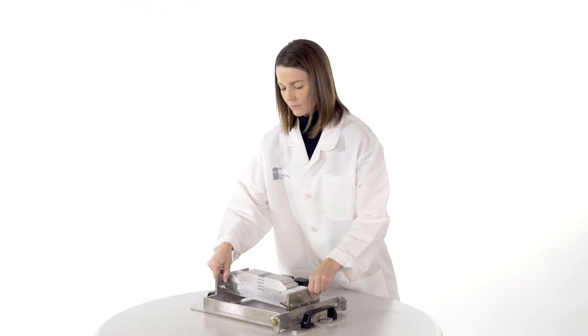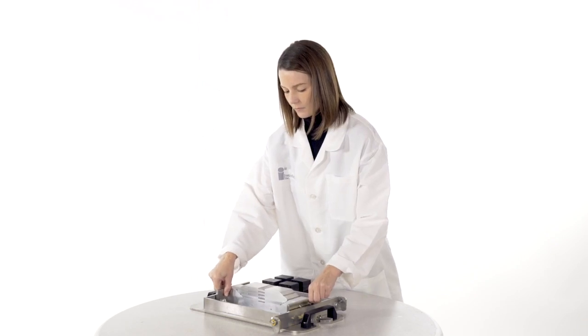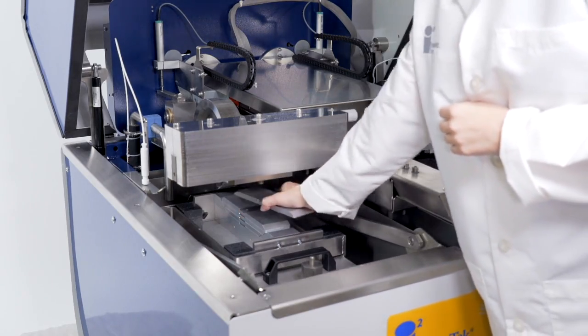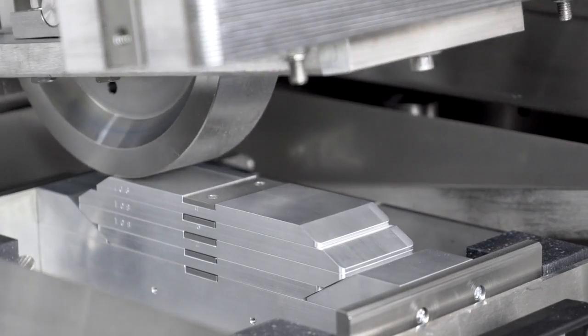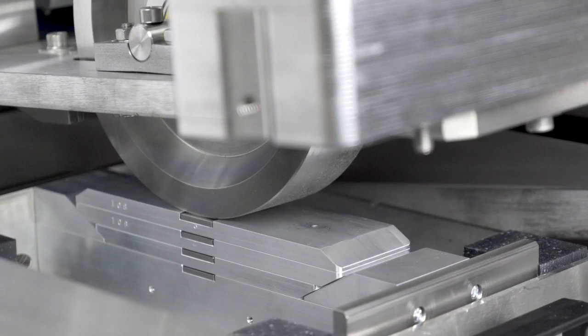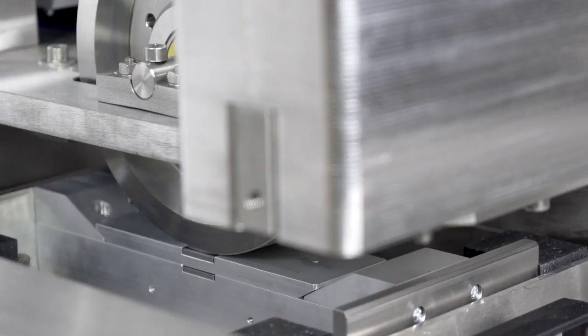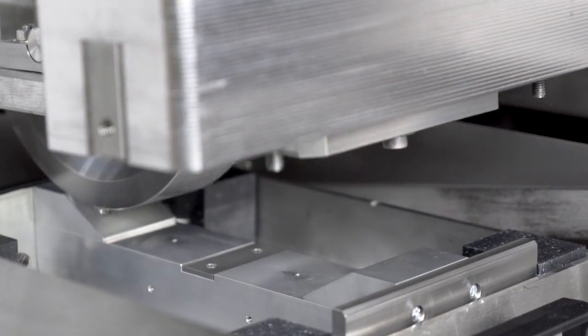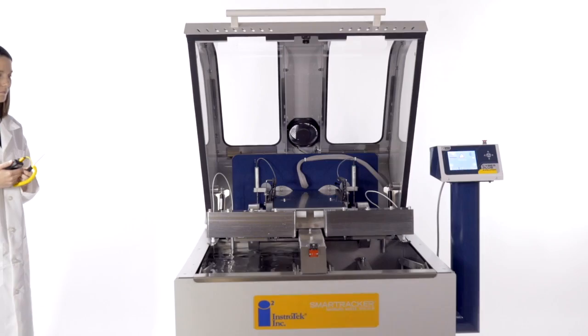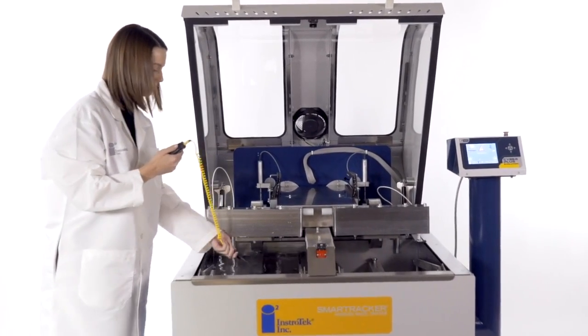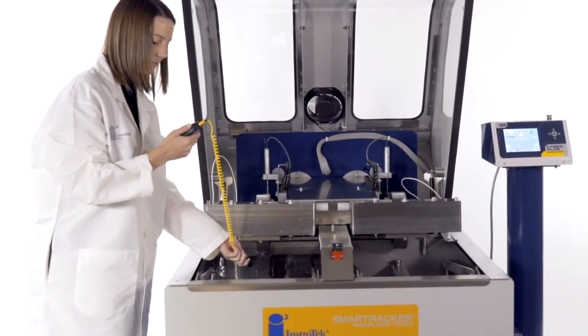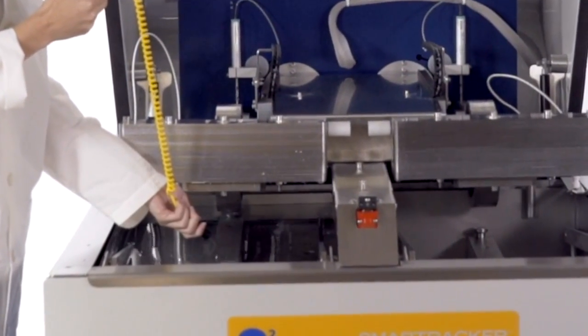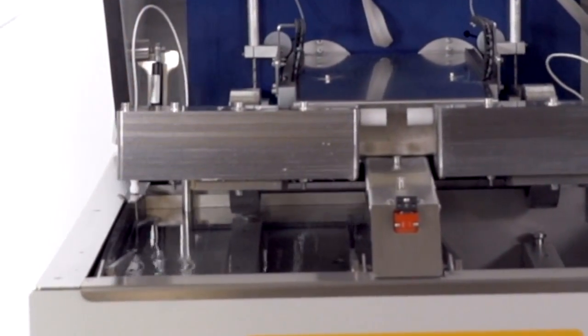The HWT Pro height indicator uses multiple spacers to verify the Hamburg's height transducers. Height measurement verification is taken in place instead of outside the Hamburg unit. This allows for a more realistic and accurate height sensor or LVDT verification. The HWT Pro NIST traceable thermometer measures the water temperature of each tank in multiple locations close to the Hamburg temperature sensor and close to the sample.